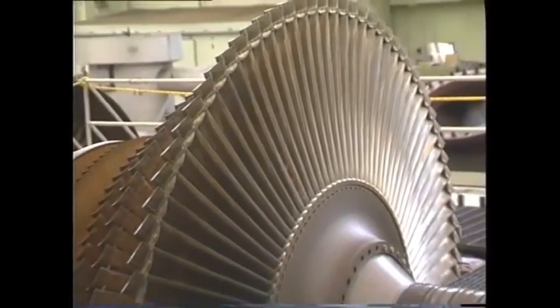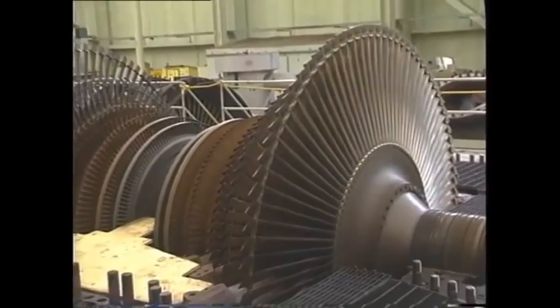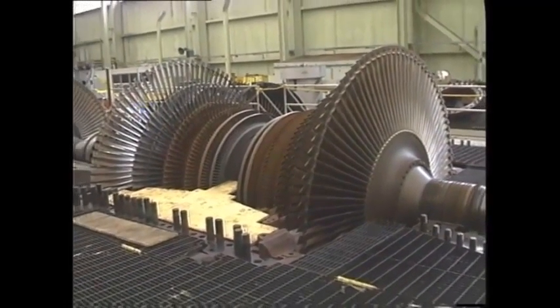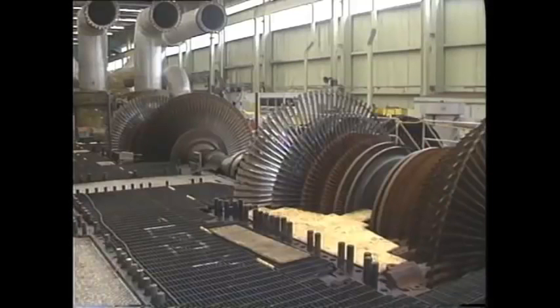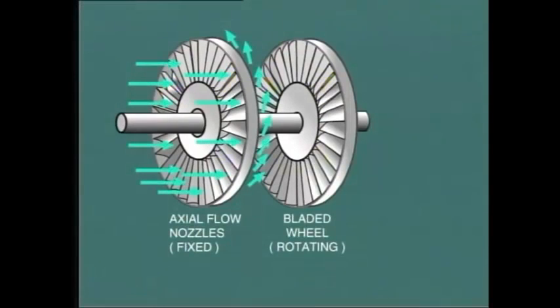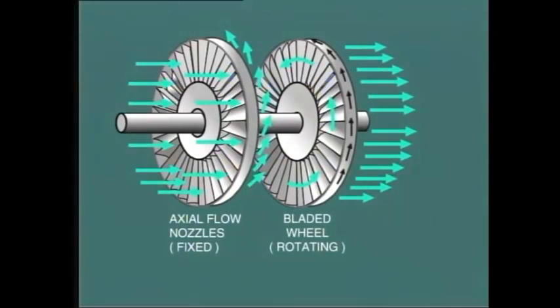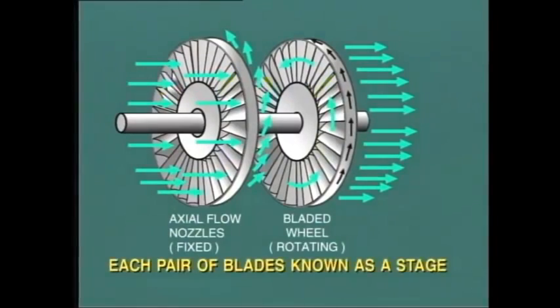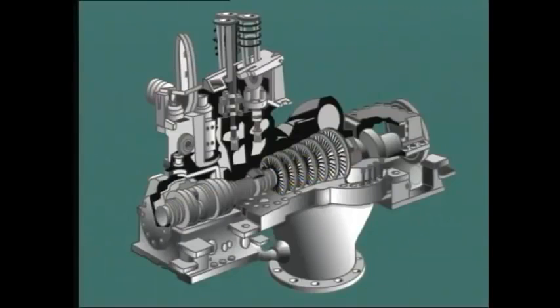Well, the simple answer is that the turbine blades are designed to take advantage of the decrease in steam pressure and consequent increase in steam velocity. As we know, the heart of the turbine, the bit that makes it work, is the relationship between the fixed and moving blades. The fixed blades guide the steam onto the moving blades. As the steam passes through the moving blades, it causes the disc to which they are attached to rotate, and consequently the shaft rotates. Each pair of stationary and associated moving blades are known as one stage. Most steam turbines contain many stages of blading. In this example of a single-cylinder machine shown here, we have 7 stages.